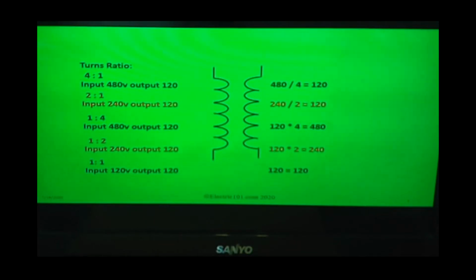Now how the turns ratio works is pretty simple. If we have a turns ratio of 4 to 1, what that actually means is there are 4 coils of wire on the primary winding for every 1 coil of wire on the secondary winding. 4 to 1. So if I have a voltage going in on the primary of 480, my power coming out on the secondary is going to be 120.